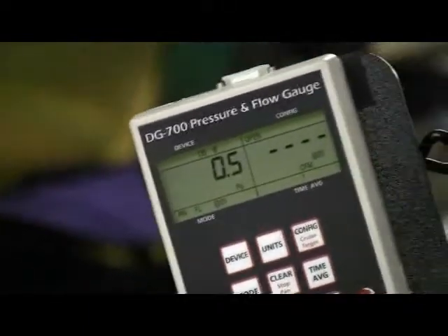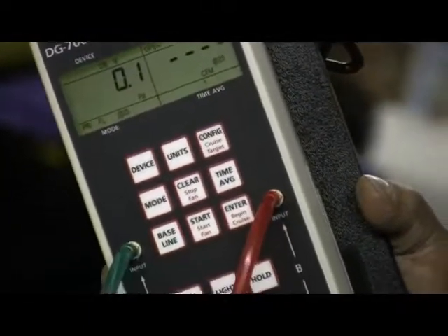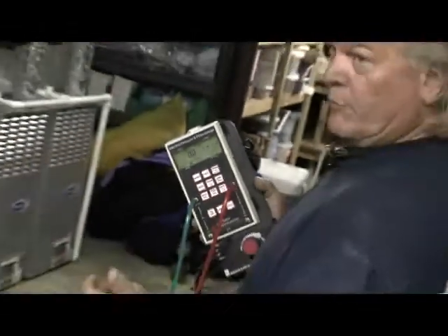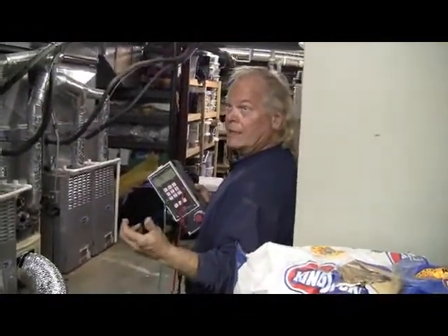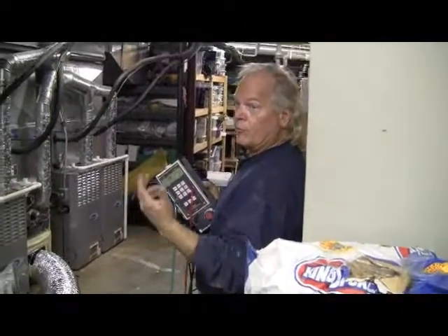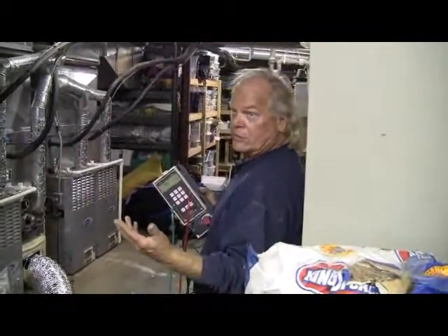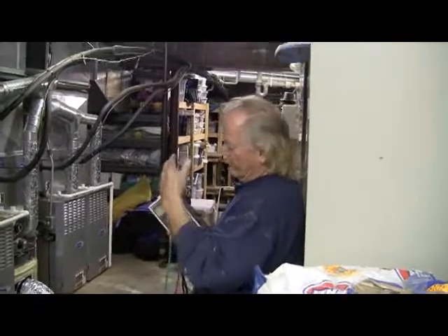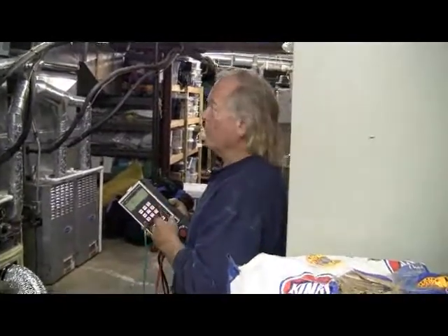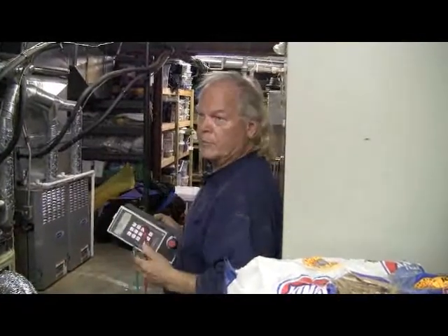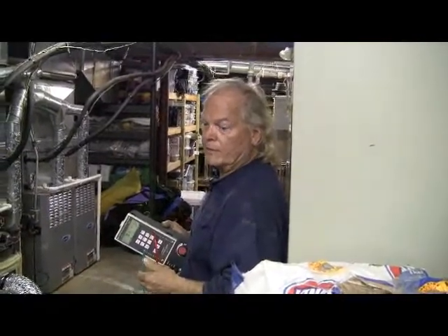With the fan on as hard as it'll go, we're getting a pressure of 6.9 pascals and a flow rate of about 2,120. So these ducts leak enough that we're not actually able to create a pressure differential of 25 because we have so much leakage. We can mathematically extrapolate what the leakage would be if we could reach 25, but we now know that these ducts leak pretty badly, and there's a real opportunity to seal them.